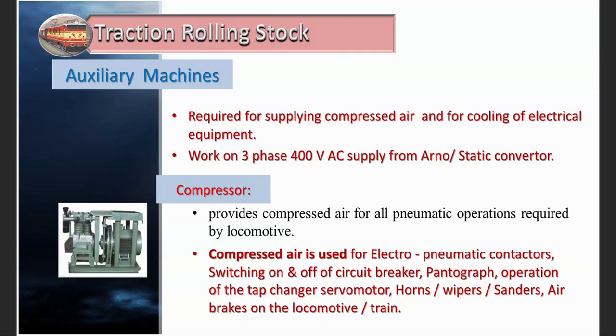As per the rule, the overall temperature should not go beyond 80 degrees centigrade. So efforts are made to design the auxiliary machines so that a sufficient amount of fresh air is blown over those equipments which are getting heated during the service.